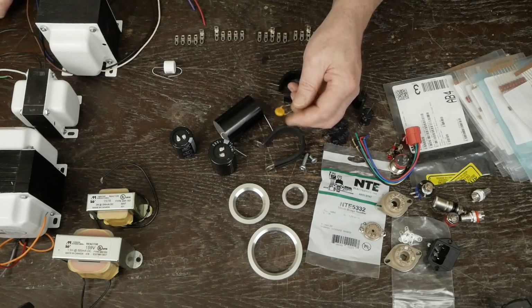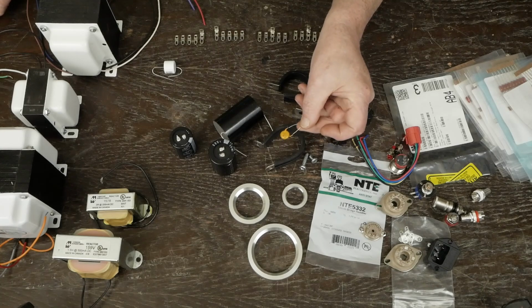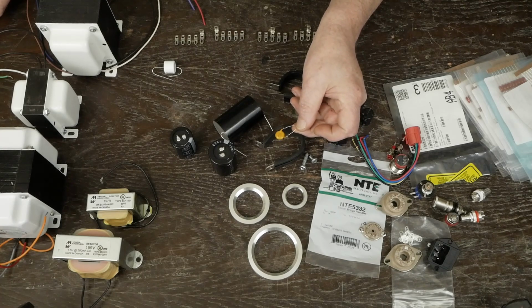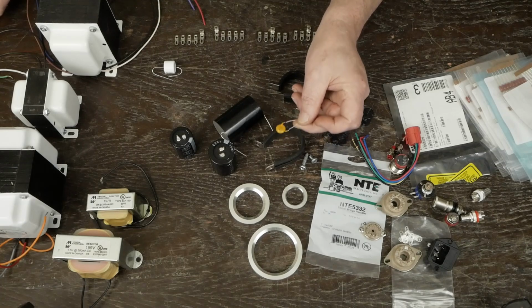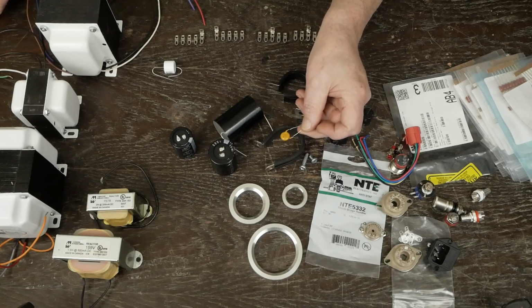The other thing you're going to need is an XY safety cap to put across the power switch, mainly to get rid of a pop noise when you turn the power on and off. You do want to use these XY safety ones because they're designed so that if they do have an issue, it's not going to cause a safety hazard.